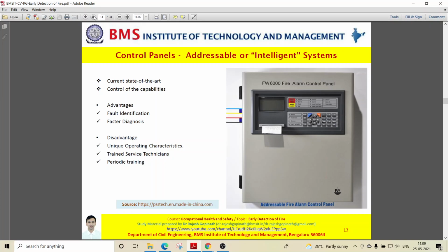Now, the best aspect of this system is that if, in your intelligent system, any detector becomes dirty over time due to accumulation of dust, or gas gets deposited, the microprocessor built into the system will understand that the capability has reduced, and having recognized it, will send out an alert. This alert is a maintenance alert saying there is a fault in one of the systems that has to be rectified. That remains the biggest advantage of this system. A faster diagnosis will always help in better troubleshooting and can prevent hazards.